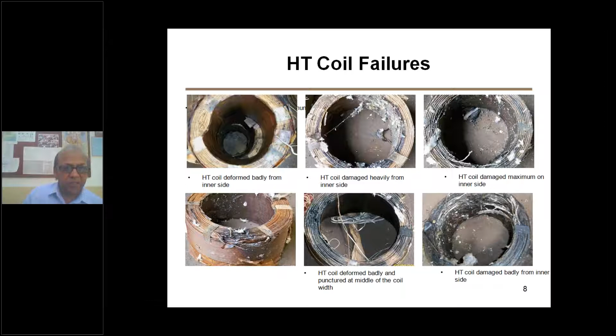And this is again between spacers, you see the failures are there in the coils. Everywhere between the spacers failure occurs in all HT coils. Now come to what is happening. We analyzed systematically thermal stresses, then electrical stresses, partial discharges, and mechanical stresses. Now thermal stresses and electrical stresses do appear, and mechanical stresses are very important when it comes to the type of the conductor to be used.